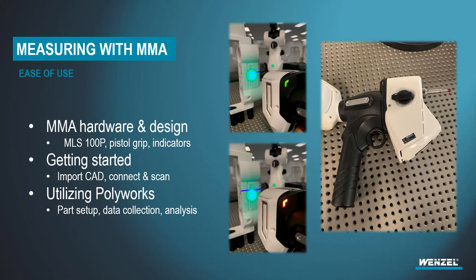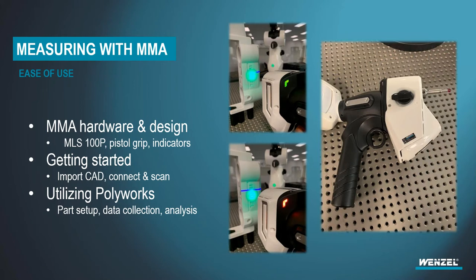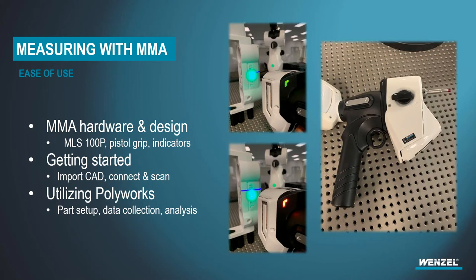So it is a manually operated device. The programming can be done in the software. If you have repeatable parts, you can create a program in the software. But you are your own driver. You are your own controller. There's also visual indicators on the scanning head. If you notice the two images on the left, the top one is green. And you can kind of see the green is an indicator light that tells me that I'm in the range. It's collecting good data. There's also a faint blue laser line that you see there. And then there's the green dots.